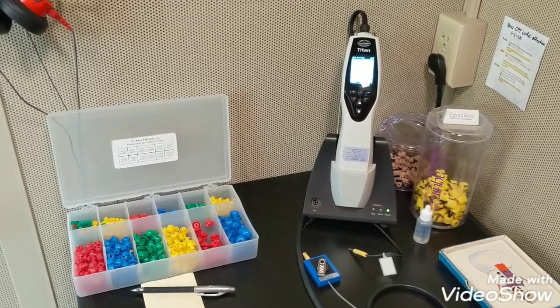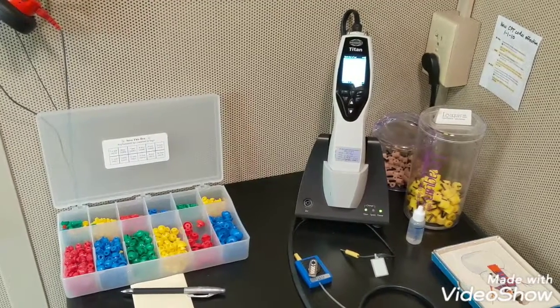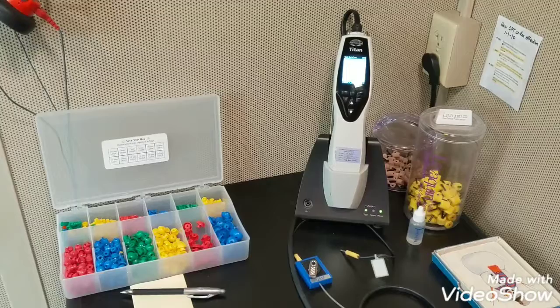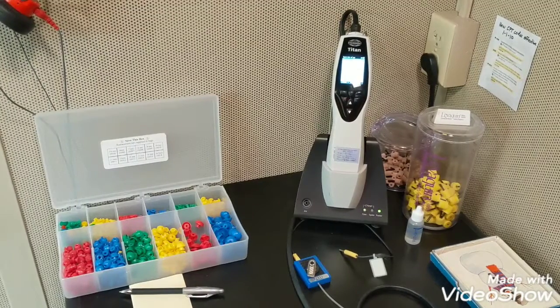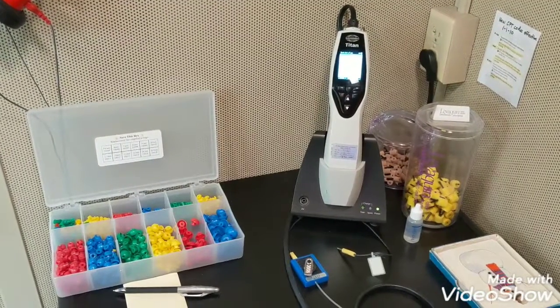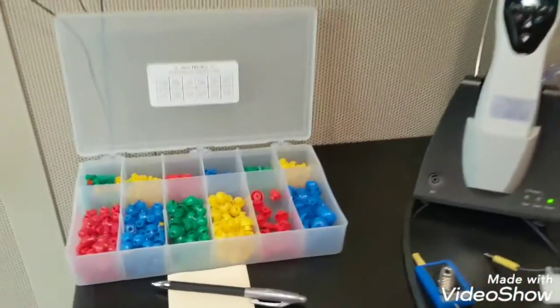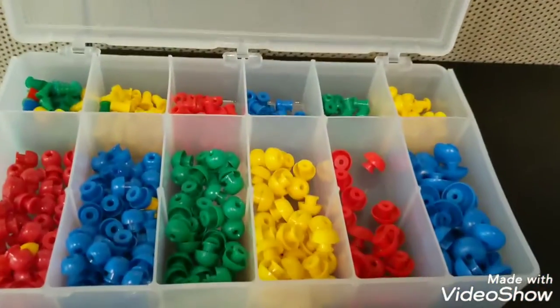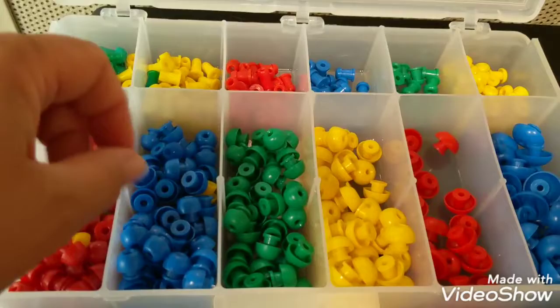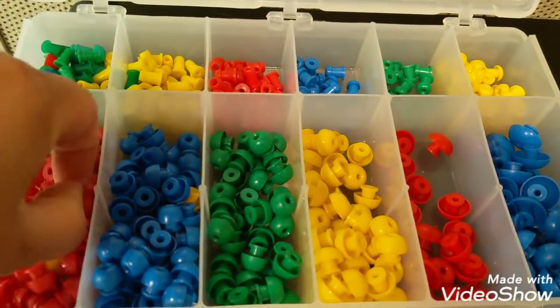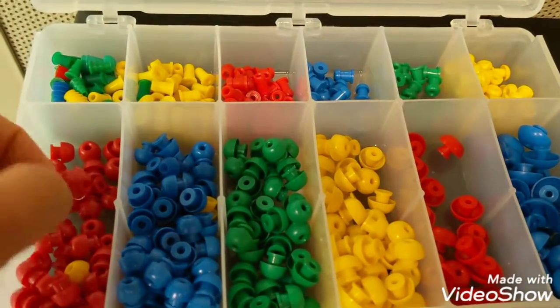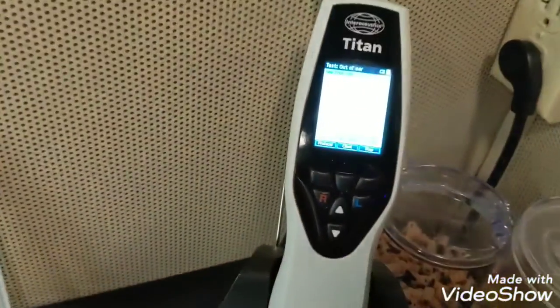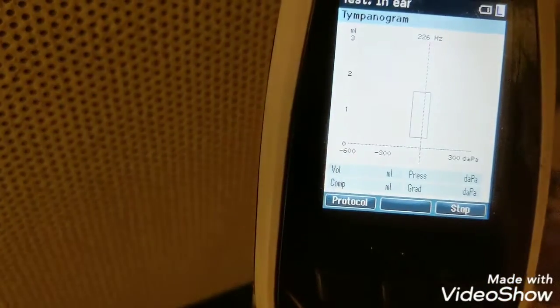Going to show you is for measuring tympanograms. Tympanograms measure the movement of the eardrum. So what I do is I select a probe tip that measures the size of the ear canal, and I have selected one that is for my ear canal size. And then I place that probe tip in my ear, and I'll show you what happens as soon as I put that in.